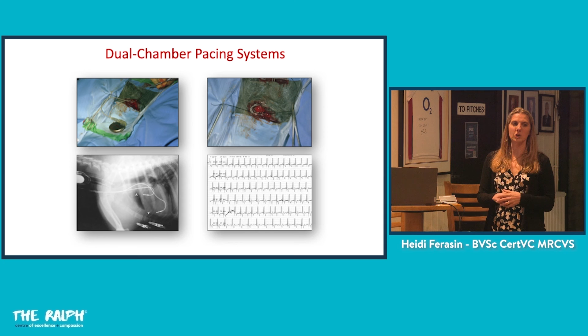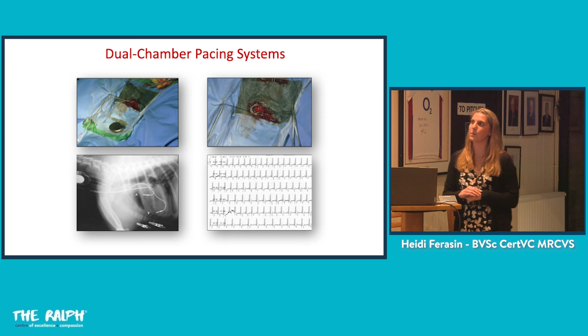If it's beating at 50 metronomically, we're happy. Sometimes these dogs have an intrinsic rhythm underneath, so the pacemaker will sit back and wait, and then it will kick in again, so sometimes the rate can be higher. When they come back in 14 days, we reprogram, reinterrogate that pacemaker, check its functions, and turn on something called rate responsive mode. Rate responsive mode allows the pacemaker speed of pacing to change dependent on the physical activity and demand of the patient. So we can set it, for example, to beat between 60 and 120, dependent on the need for the patient. And we do that when we know everything's fixed and we're happy it's not going to detach.